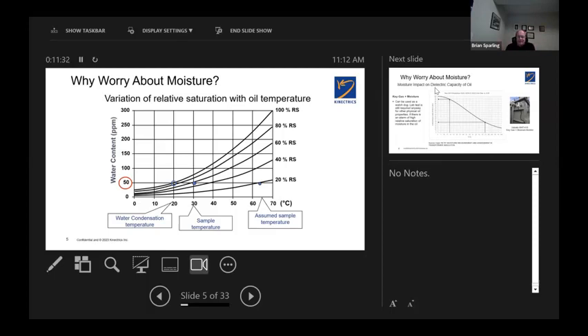The relative saturation interacts between the oil and the paper. Because remember, paper acts like a big sponge inside there. Oil and water don't mix. What the oil doesn't want, the paper's there to soak up like a big sponge. But when it gets hot, it pushes the water into the oil. So when you're taking samples, find a way to take the temperature of the sample at the time you take the sample, not when the sample's back in the truck, and not when it's back in the shop, and you'll be able to understand how saturated that oil is.